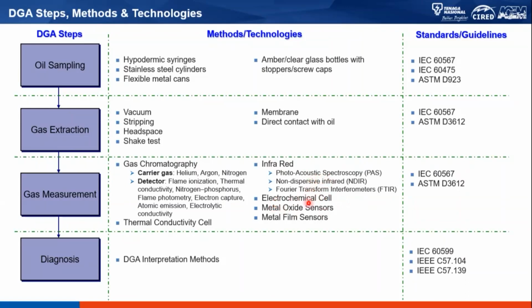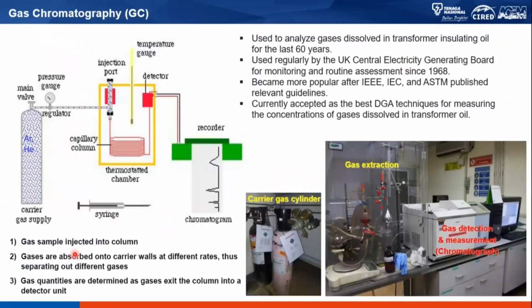There is also a technique called electrochemical cell, metal oxide sensors, and metal film sensors. Normally, all three of these, together with thermal conductivity cell, are used with membrane or direct contact with oil gas extraction techniques. Later on, we're going to look into the DGA interpretation methods as part of the diagnosis of the insulating oil.